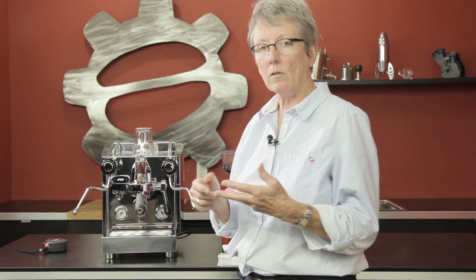Steam arm over here, water arm right here, your lever to activate, three-way solenoid valve, and the PID that I was talking about. The PID on this machine, you can change it from Fahrenheit to centigrade. You can also change the temperature of the heat exchanger.